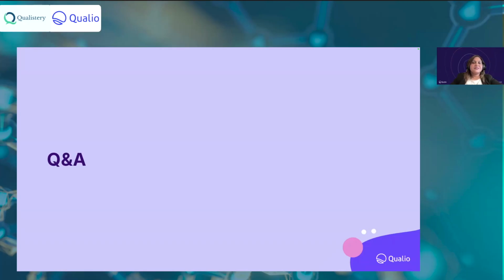Maybe Heinz may have more on this, but I'll provide some of the information which I know about it. Whatever the specific testing or requirements, during the design verification and validation you will already be setting up those test cases, correct? Based on that, you perform the testing and see to what extent it can be used, and then identify the usage period based on your intended purpose. If there are any reusable medical devices, for example hardware, you need to make sure what factors are associated with the usage of the device, and if anything affects the product quality, you need to define that.